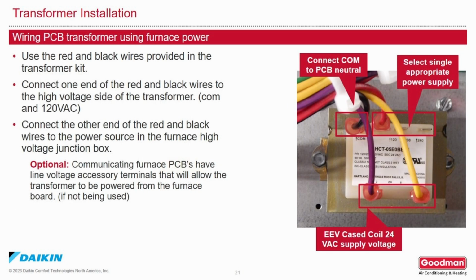Wiring the PCB transformer using furnace power. Use the red and black wires provided in the transformer kit. Connect one end of the red and black wires to the high voltage side of the transformer, common and 120 volts. Connect the other end of the red and black wire to the power source in the furnace high voltage junction box. Communicating furnace PC boards have high voltage accessory terminals that will allow the transformer to be powered from the furnace circuit board if they're not being used by something else.